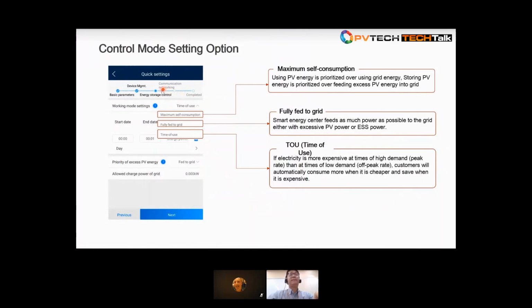For the working modes in the 5-step quick commissioning, there are 3 types of control mode. The first is maximum self-consumption, which aims to use PV energy as much as possible. In some countries, feeding to the grid doesn't earn much money because the feed-in tariff is very low, so it makes more sense to maximize self-consumption of solar power.